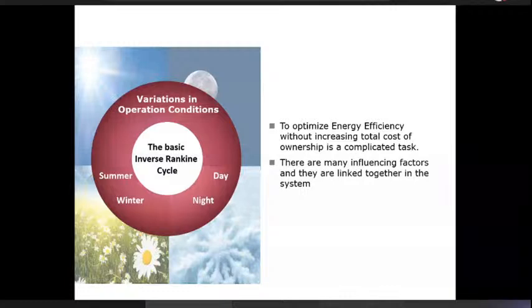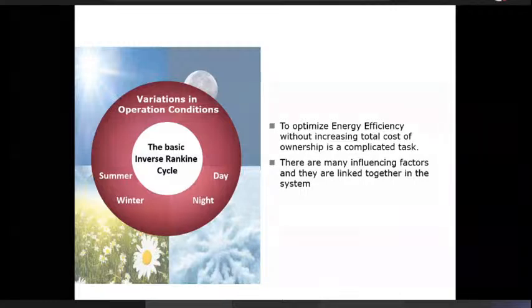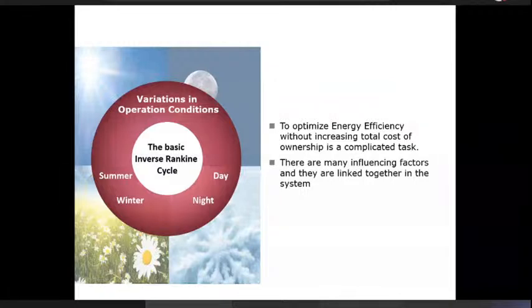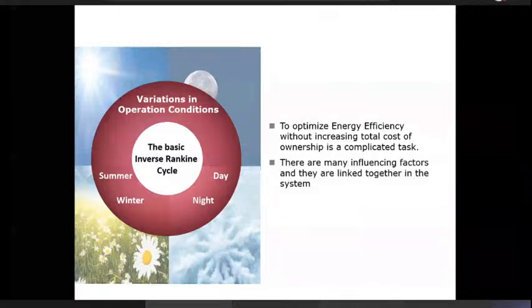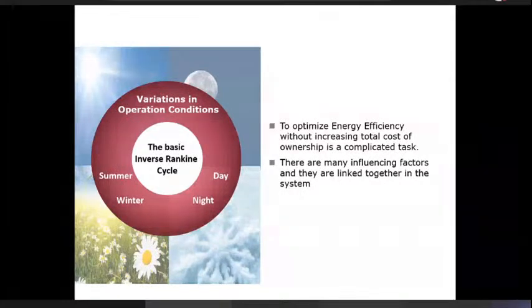However, when we look at the impact on the environment, that number, if we hit 3.3 and it is being sent to market with 3.3, is not truly representative of the amount of energy that this product is going to consume. A well-optimized system at 35 degrees outdoor air temperature will not behave the same at 45 degrees outdoor air temperature. And what is the percentage derating? What happens when the temperature goes up? That's an influence of design. How robust is the design?